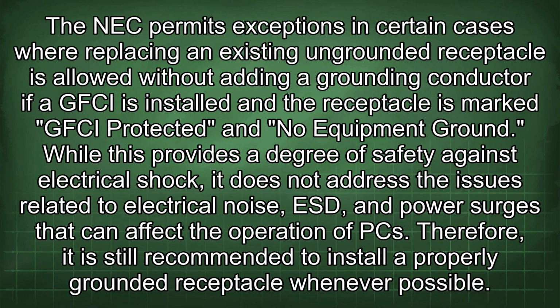The NEC permits exceptions in certain cases where replacing an existing ungrounded receptacle is allowed without adding a grounding conductor, if a GFCI is installed and the receptacle is marked "GFCI protected" and "no equipment ground." While this provides a degree of safety against electrical shock, it does not address the issues related to electrical noise and power surges that can affect the operation of a PC. Therefore, it is still recommended to install a properly grounded receptacle whenever possible.